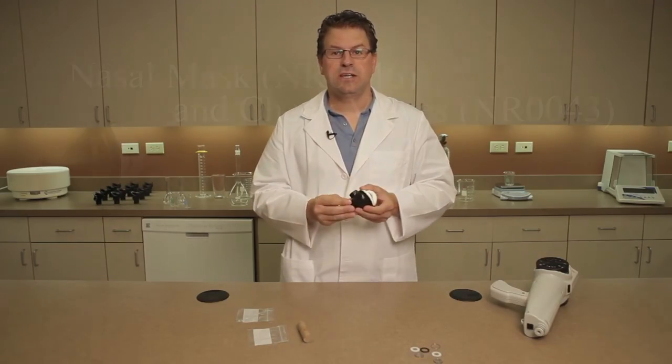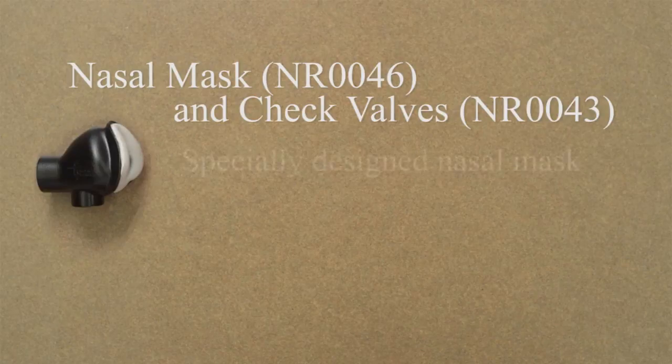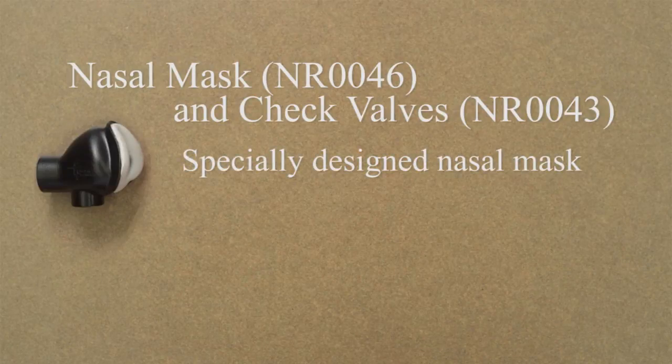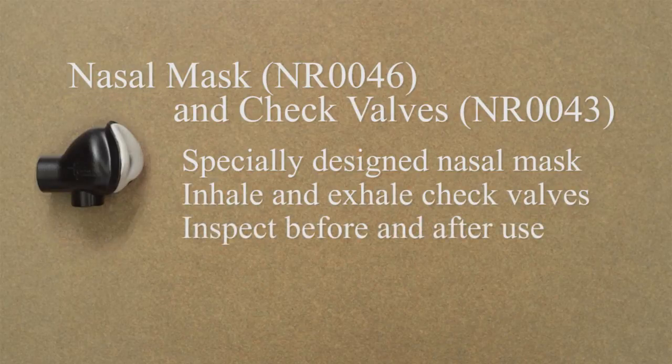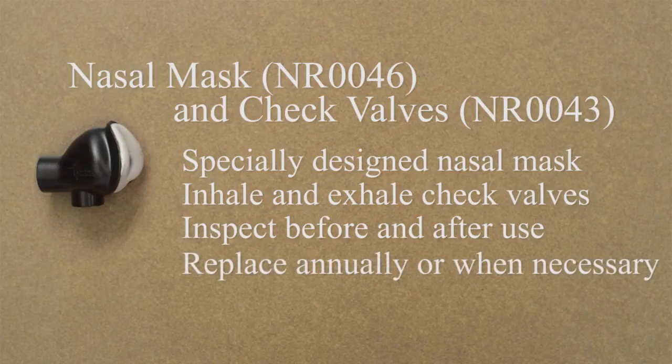Let's review what we've just seen. The Nasal Ranger mask is a specially designed nasal mask for optimum performance of your Nasal Ranger Field Olfactometer. The inhale and exhale check valves on the nasal mask should be inspected before and after each use. Replace the valves if they're damaged or dirty. Annual change is recommended.